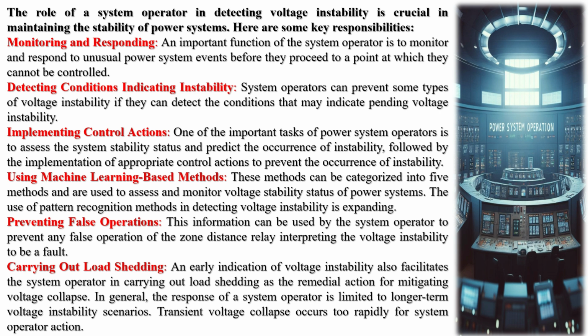Using machine learning-based methods. These methods can be categorized into 5 methods and are used to assess and monitor voltage stability status of power systems. The use of pattern recognition methods in detecting voltage instability is expanding. Preventing false operations. This information can be used by the system operator to prevent any false operation of the zone distance relay interpreting the voltage instability to be a fault. Carrying out load shedding. An early indication of voltage instability also facilitates the system operator in carrying out load shedding as the remedial action for mitigating voltage collapse. In general, the response of a system operator is limited to longer-term voltage instability scenarios. Transient voltage collapse occurs too rapidly for system operator action.